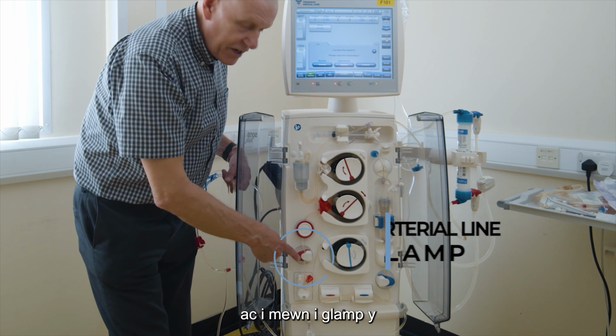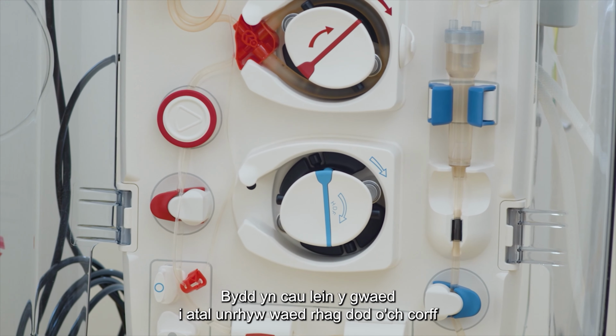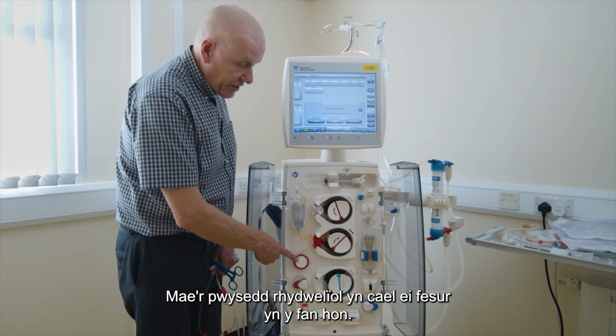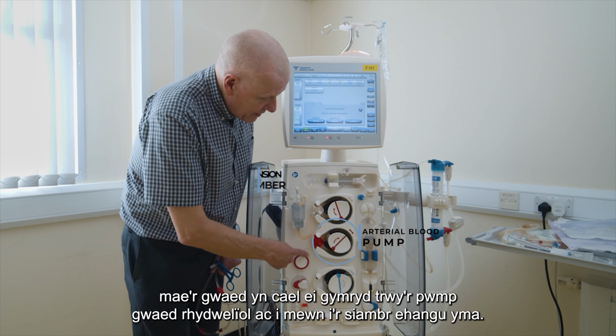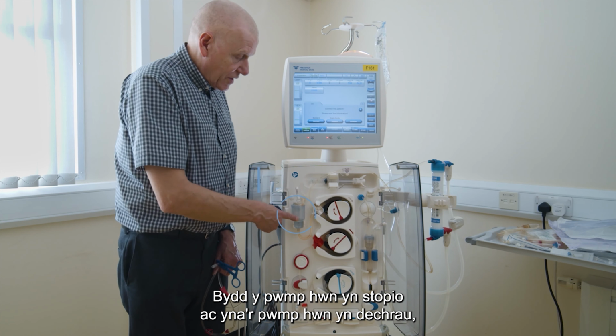In through the arterial line clamp, which clamps the line in the event of a problem with the machine. It'll close the blood line to stop any blood coming from your body if there's an alarm on the machine. Arterial pressure is measured at this point here. From here, the blood is taken through the arterial blood pump into the expansion chamber here.